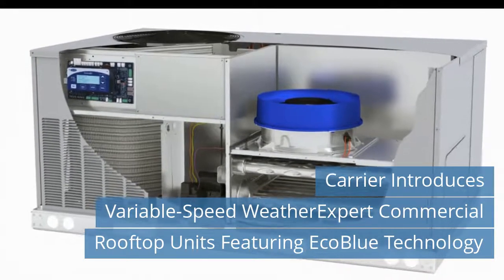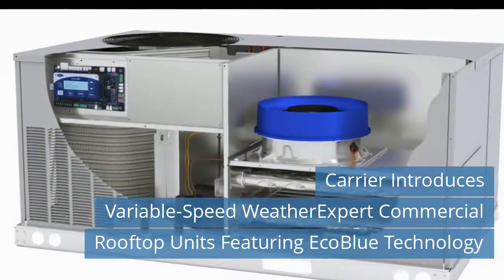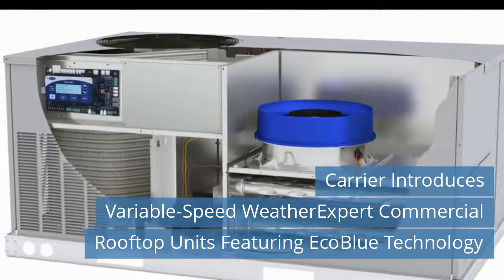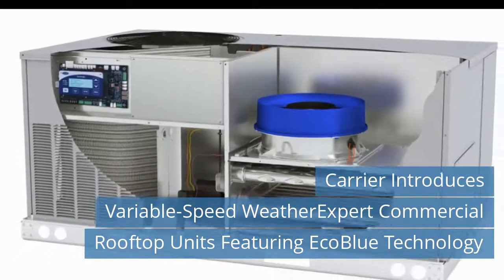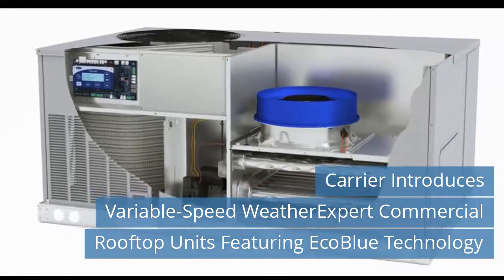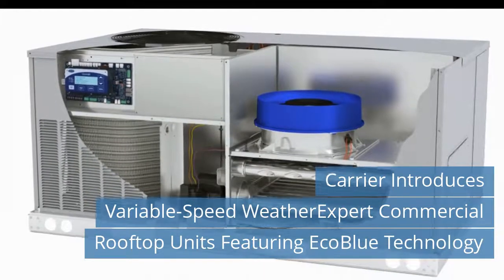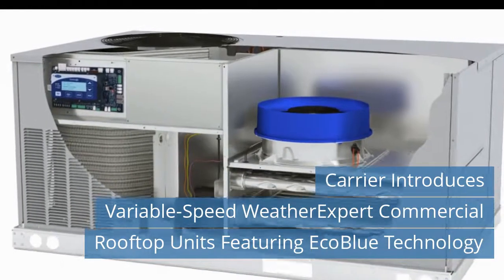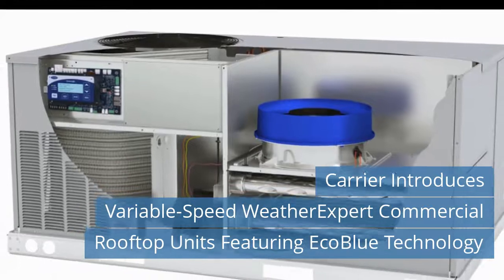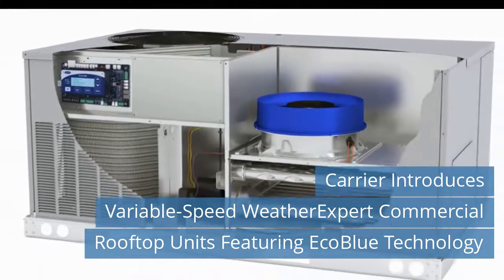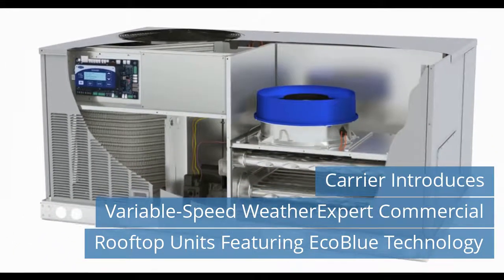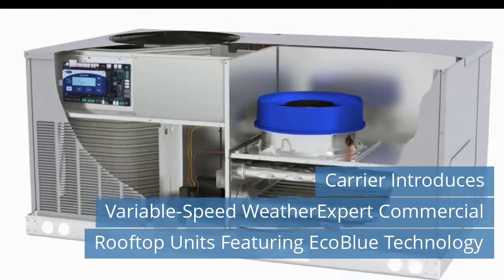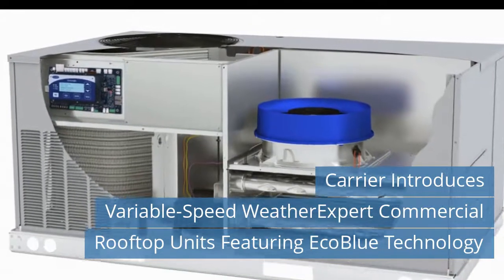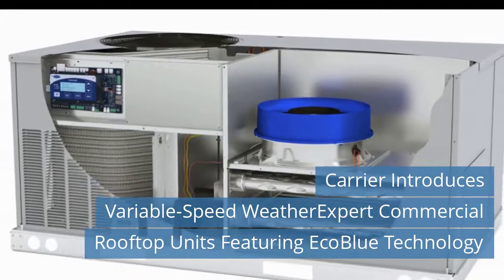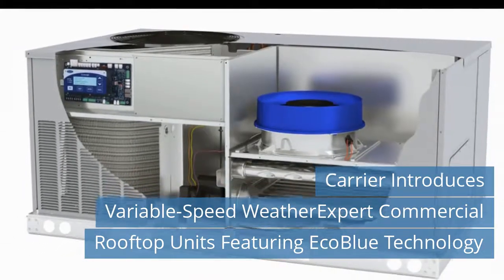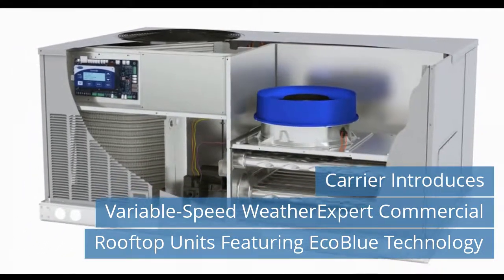Most notable of EcoBlue technology's many features is the exclusive beltless direct drive vane axial fan system, an industry first for rooftop units when introduced in 2018. This patented technology replaces traditional belts, pulleys, and forward curve fans with a simpler, more compact design, with 75% fewer moving parts. The outdoor fan system's high-density composite blade fan is also an exclusive design. Both fans are dynamically balanced for quieter operation.